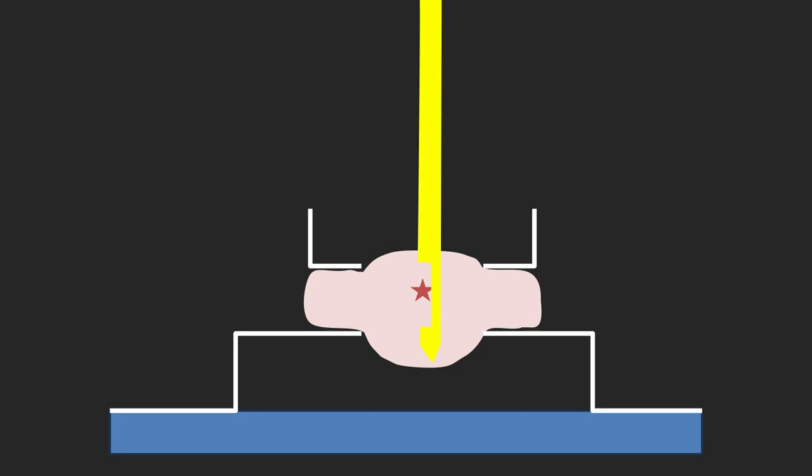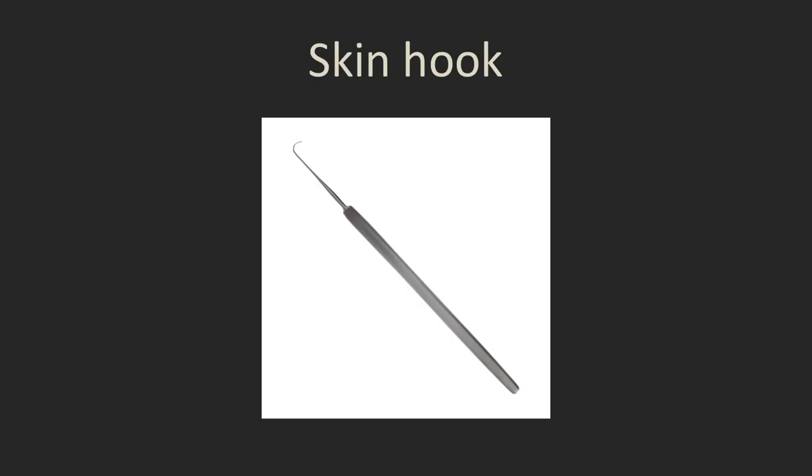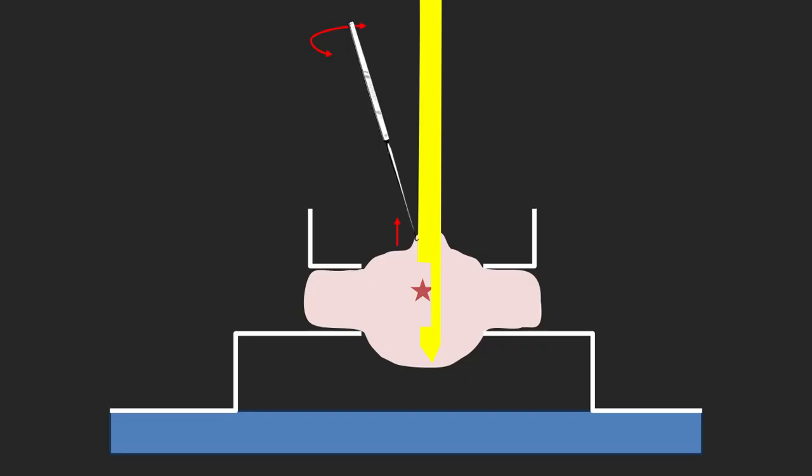So if your chamber is up and above the breast here, when you've deployed it, you can gently wind it in a little bit to get below the surface, or you can use a skin hook. So this is just something that comes from our surgical instrument department, and you just take the sterile skin hook after you've deployed the needle, but before you do the biopsies.